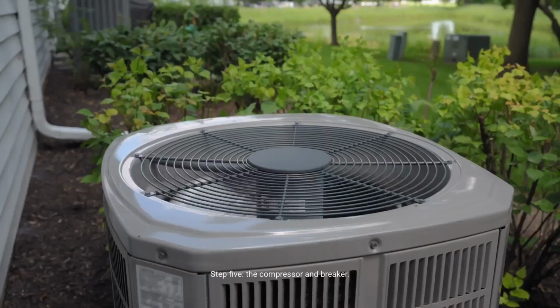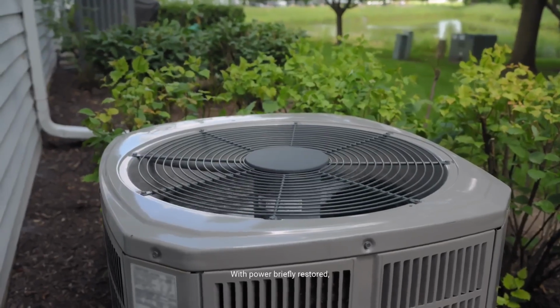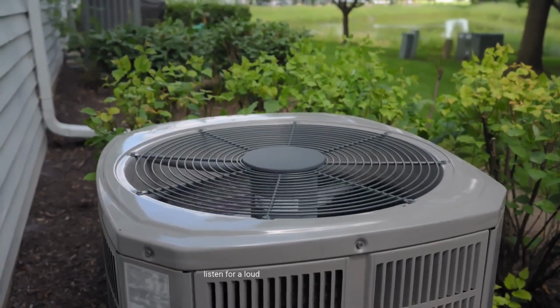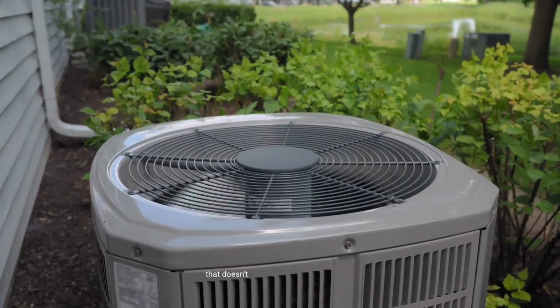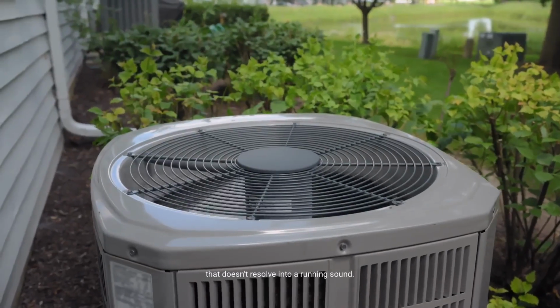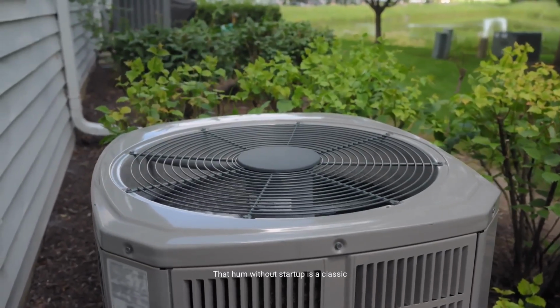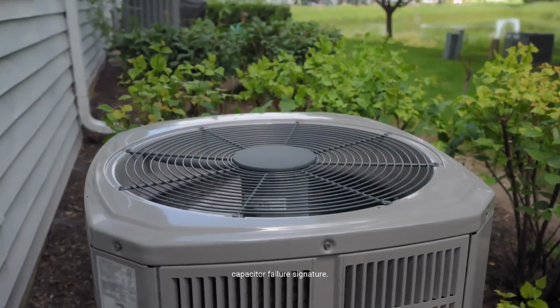Step 5. The compressor and breaker. With power briefly restored, seconds only, listen for a loud hum from the compressor that doesn't resolve into a running sound. That hum without startup is a classic capacitor failure signature.